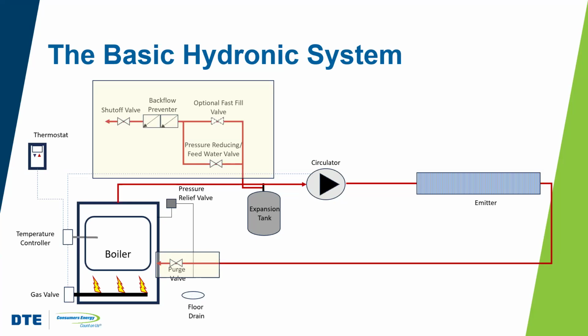You're gonna have some pressure. You're gonna have a pressure gauge there. You're gonna have a shutoff to allow for isolation. You may have a fill valve there to speed up fill, right? To have it fill a little bit faster. And then you're going to have a purge valve, right? That's going to also get rid of air in the system.